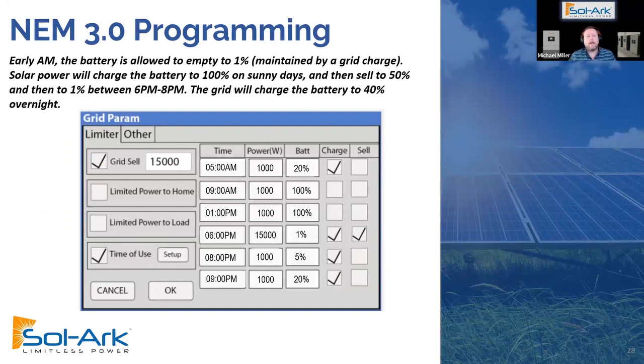So what does that look like in the actual programming screen I showed earlier? We check the grid sell box and set it up to the maximum, 15,000 watts on the 15K unit. We have time of use selected, and in the evening hours we might want to charge a little from the grid to bring batteries up to a nominal value—this depends on your comfort level and battery size; you may want more reserve power, which is up to you.